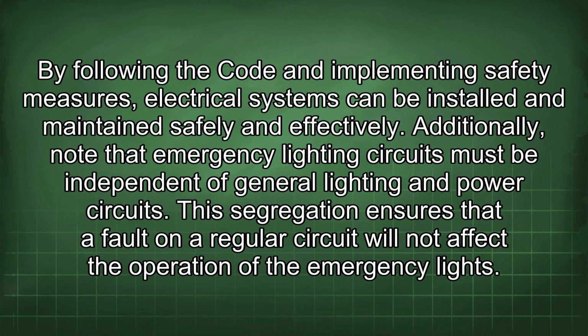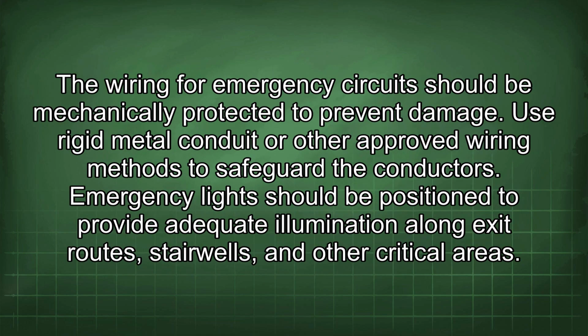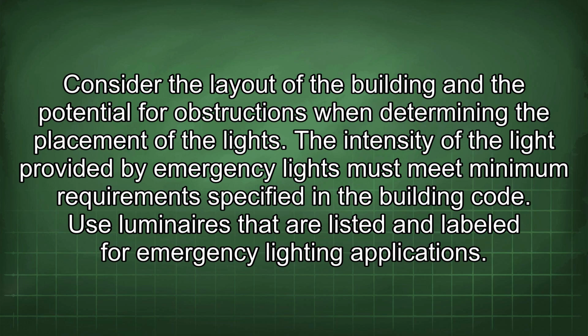Additionally, note that emergency lighting circuits must be independent of general lighting and power circuits. This segregation ensures that a fault on a regular circuit will not affect the operation of the emergency lights. The wiring for emergency circuits should be mechanically protected to prevent damage. Use rigid metal conduit or other approved wiring methods to safeguard the conductors. Emergency lights should be positioned to provide adequate illumination along exit routes, stairwells, and other critical areas. Consider the layout of the building and the potential for obstructions when determining the placement of the lights.